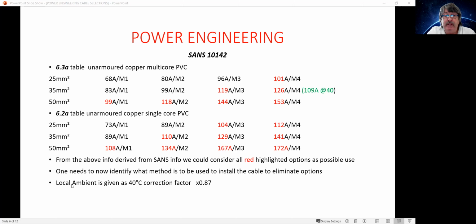We must also factor in that we said the local ambient is given at 40 degrees. And so the correction factor here is 0.87 times these values. Sorry. And we can see that the one I eventually chose, and I'll go back into a bit of the details, is 109 amps at 40 degrees, which is actually this particular one, which gives 109 amps once we do the factor correction for temperature, which we've got to do. So looking at the table, there's an option here, anything from 25 to 50 mils cable could be used.